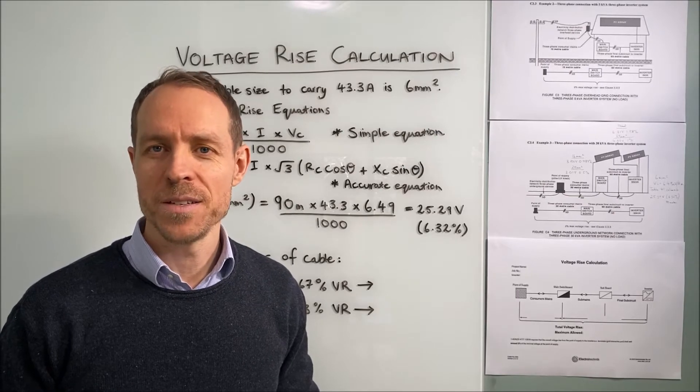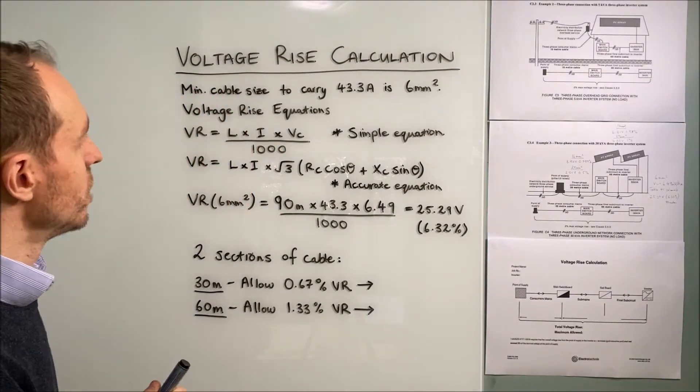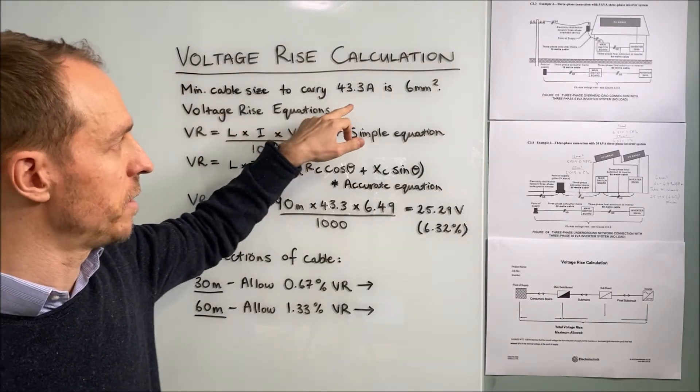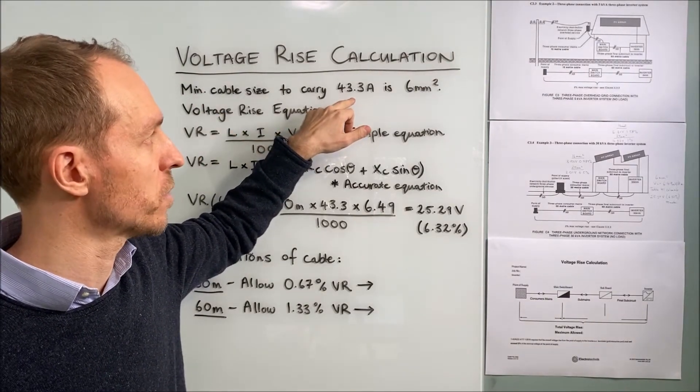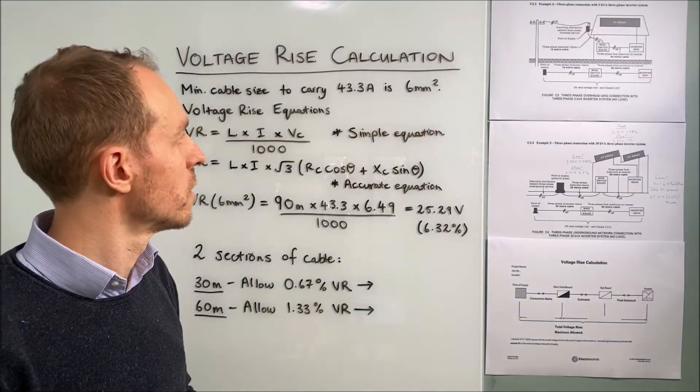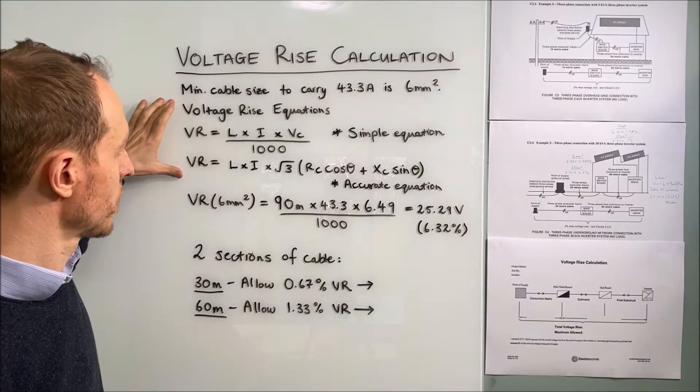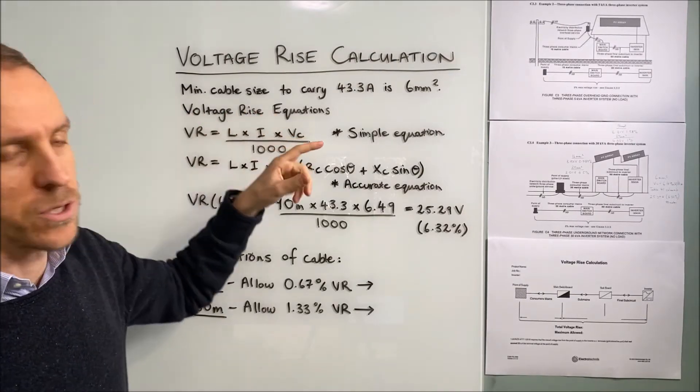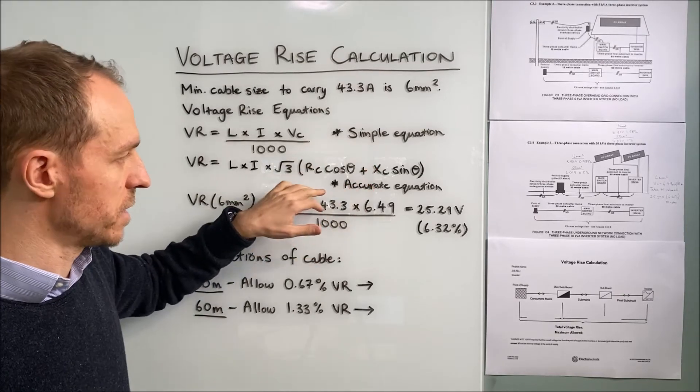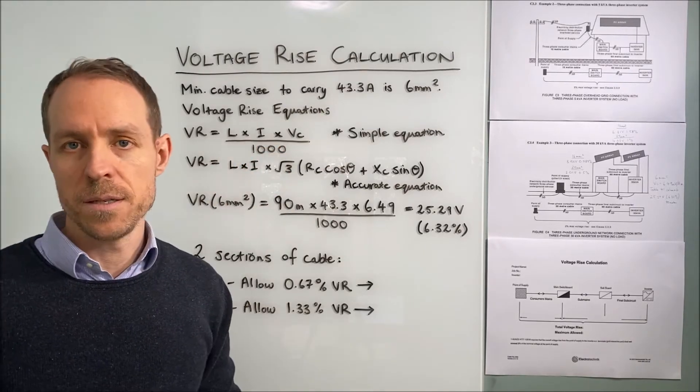Now I'm going to explain to you how to do the voltage rise calculations by hand. So we've worked out that the minimum cable size to carry the inverter output current of 43.3 amps is 6mm squared. So just to explain the voltage rise equations, there are two equations you could use. There's what we term as the simple equation and there's an accurate equation. The simple equation is obviously a lot easier to use by hand. You just need this VC value which is taken from the standard AS3008.